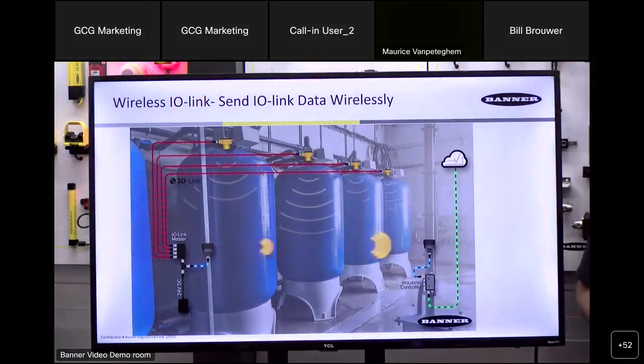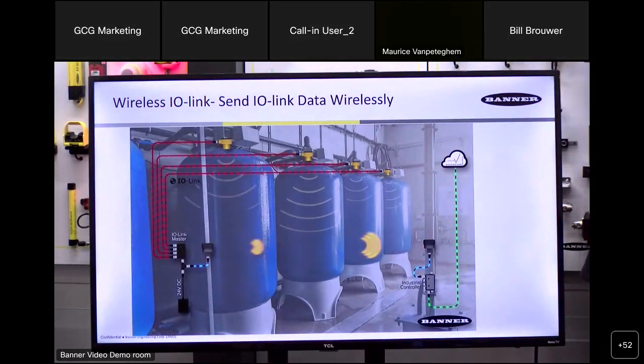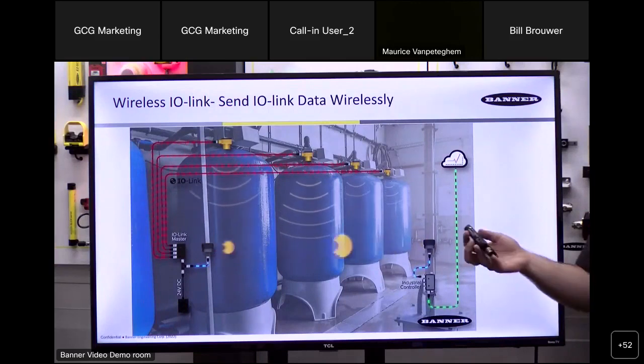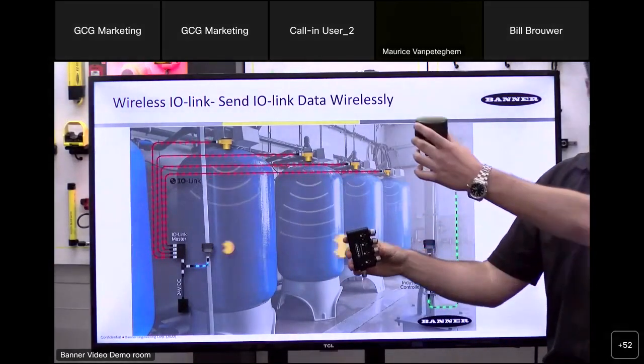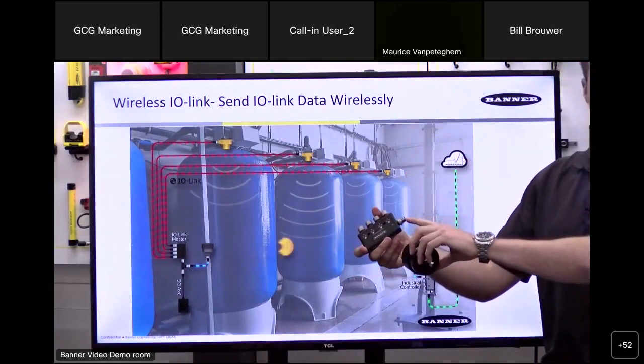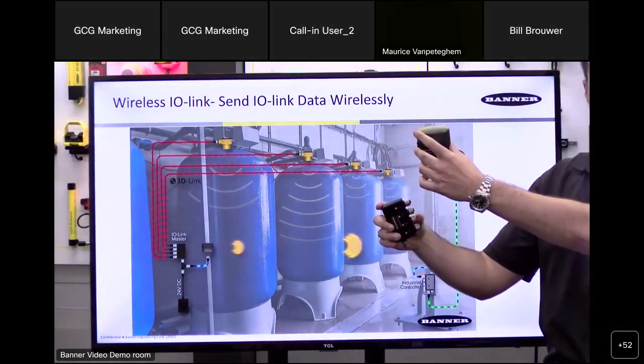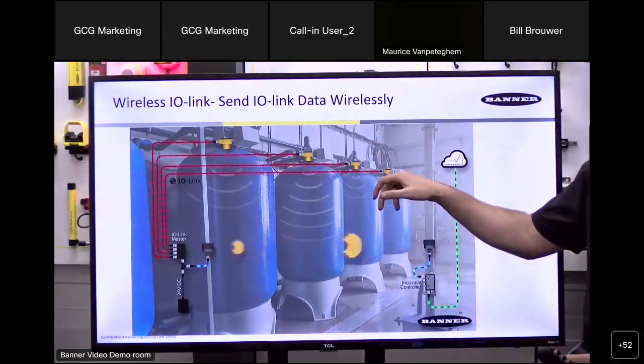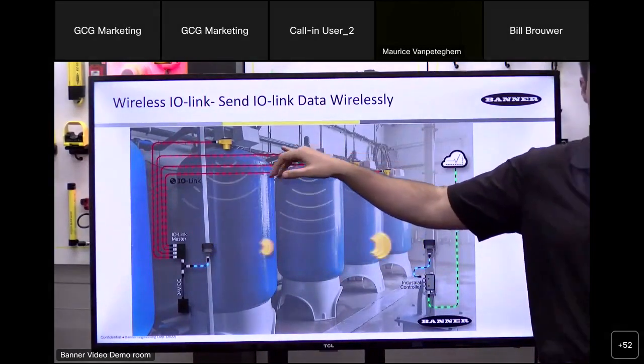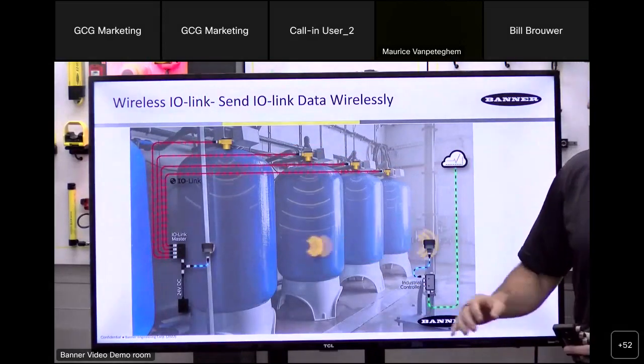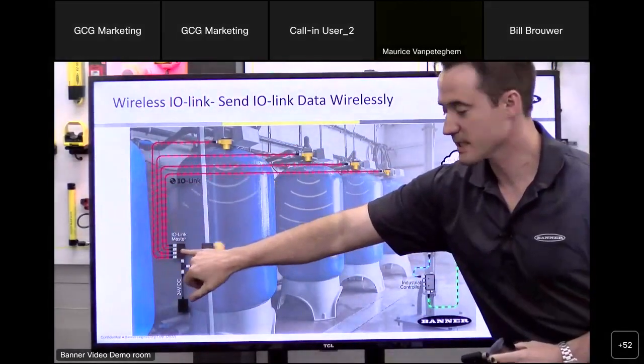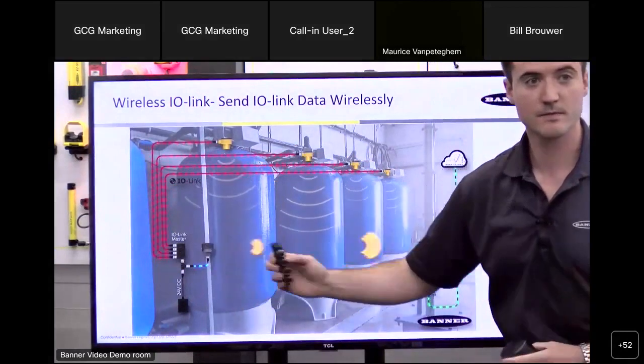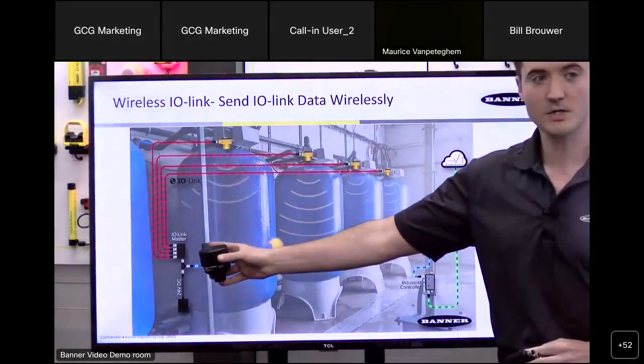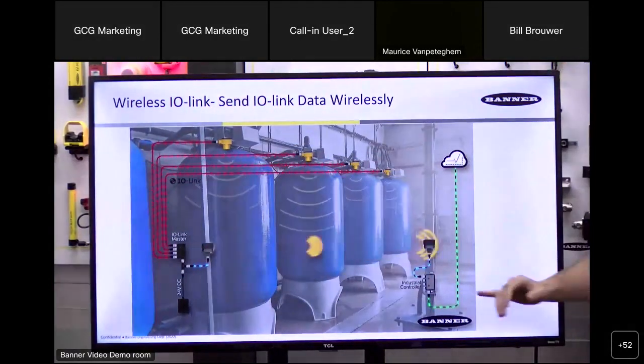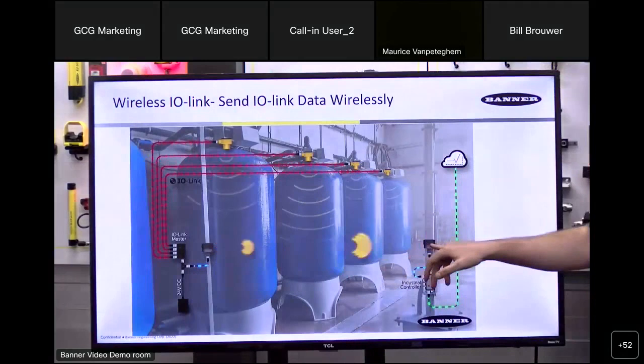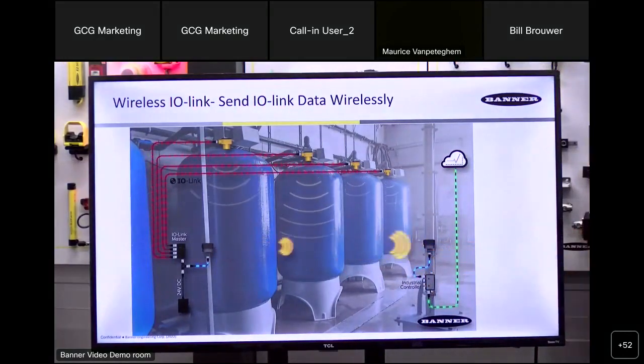What this technology also allows us to do is things such as wireless IO-Link. So deploying something where you have an IO-Link master and an R70, you have the RS-485 protocol going out to the serial data radio. And what we could do here is have some tank level sensors that are T30R IO-Link tank level sensors. We could capture that sensor data, connect it to our IO-Link master, deploy one of our R70 serial data radios, and send the data back to another R70 serial data radio across your factory.